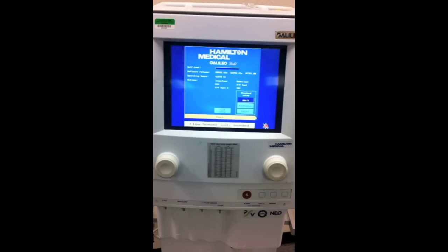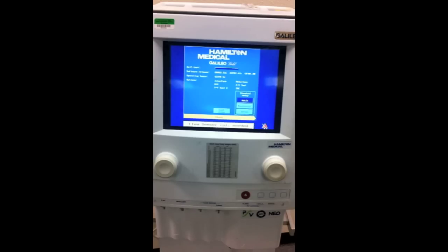Oh, I doubt it. Okay, you must have the flow sensor for this ventilator or it will not work. What this does is it measures up here the actual flow being delivered, and when we calibrate it, it's going to calibrate this flow sensor. There's little plastic flaps in here that actually open, and when the flow goes through, it can sense how much flow is going through by how fast it does that. So that goes on here.